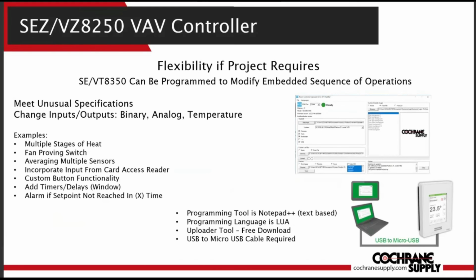Finally, the software tool to connect to the room controller is to download a program, upgrade or change firmware, load a custom standby image, or configure multiple controllers in the same way. You can configure one unit, save that configuration, then plug into the next unit, press restore, and it will configure that controller exactly like the previous one. That software is called Uploader 8000 and it's free on our website. All you need is a USB to micro USB cable, which is available at any electronics outlet.